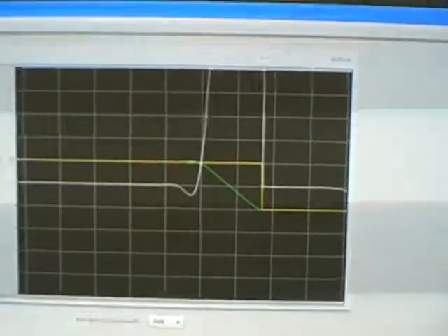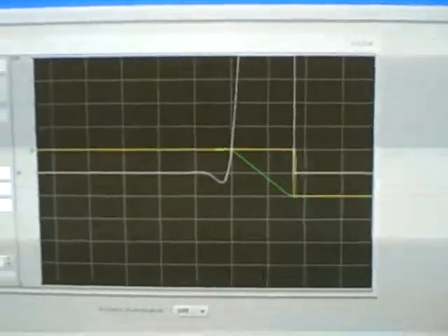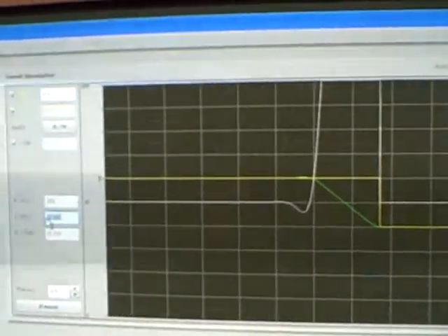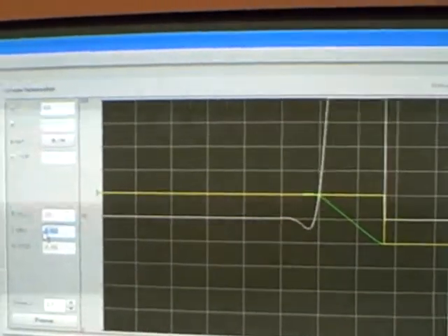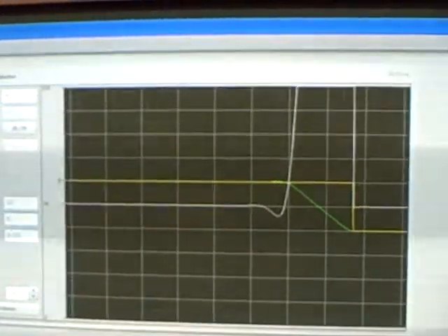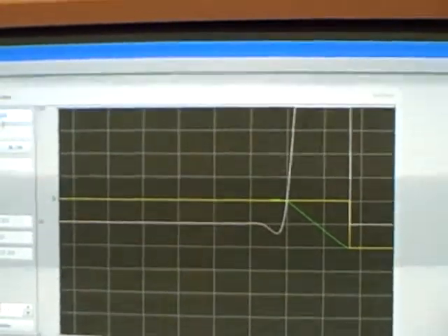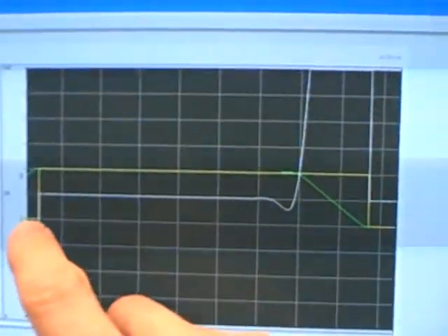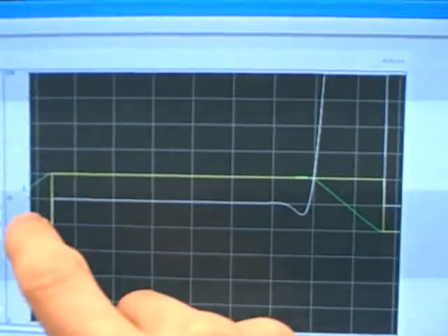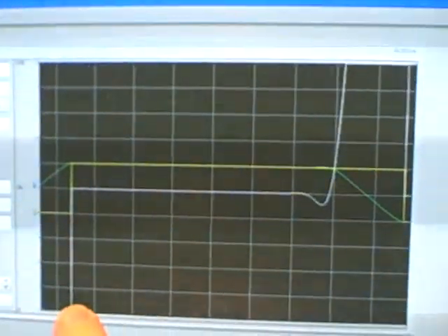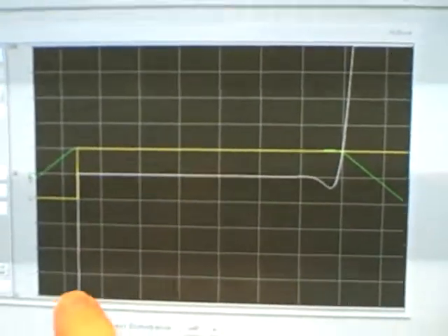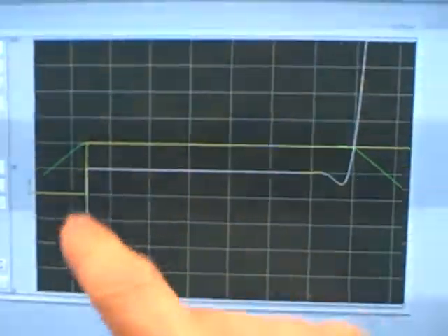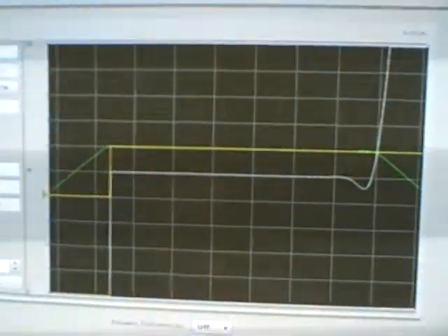I'm going to show you this. With a high gain value, I'm going to put in a small integral value. Let's say 1 repeat per minute. I'm going to go to a new set point value of 40%, and we'll see what happens. I move my set point down. My process variable now is integrating downwards. My valve is fully closed. But what's happening here is integral action is also helping to wind that valve in the downward position.